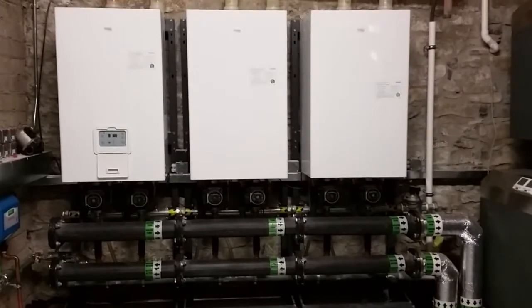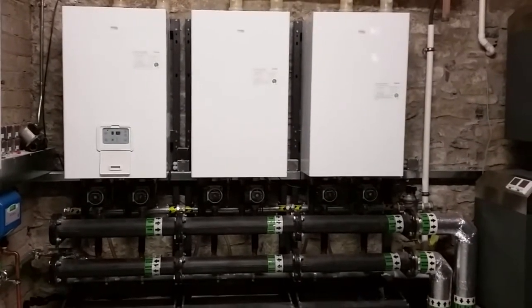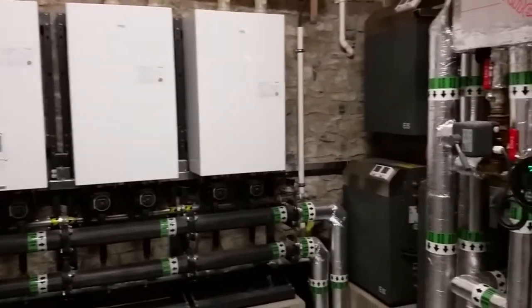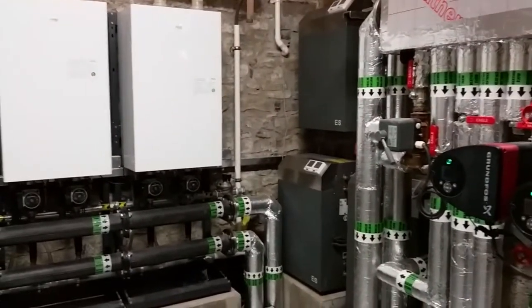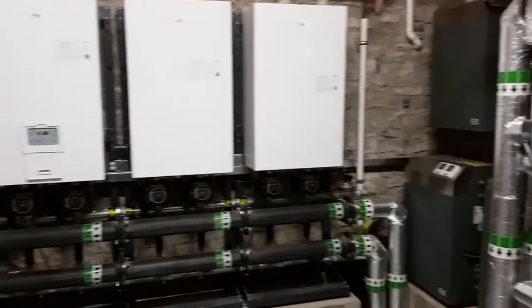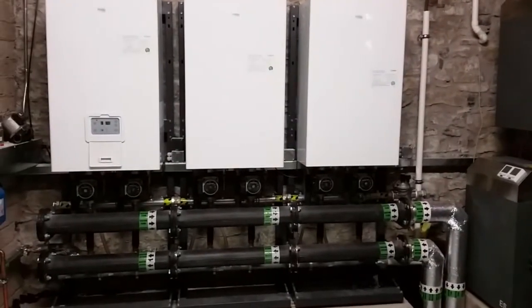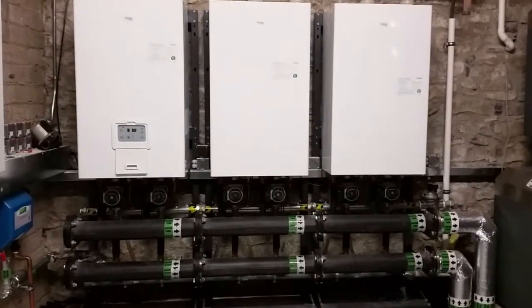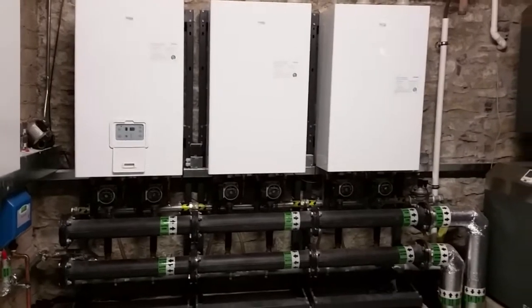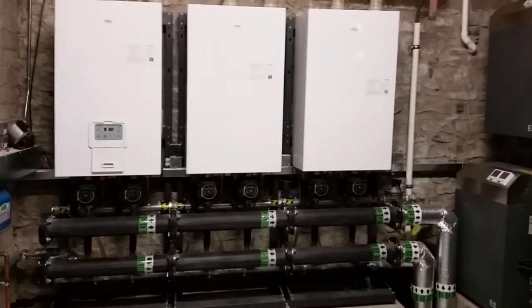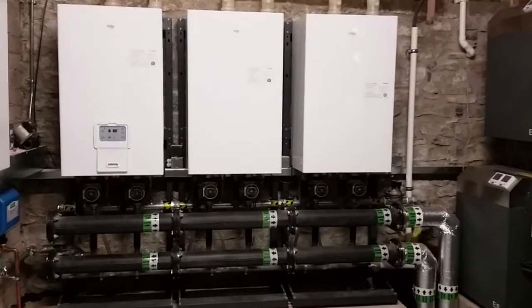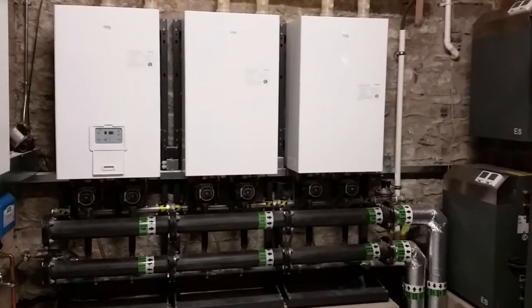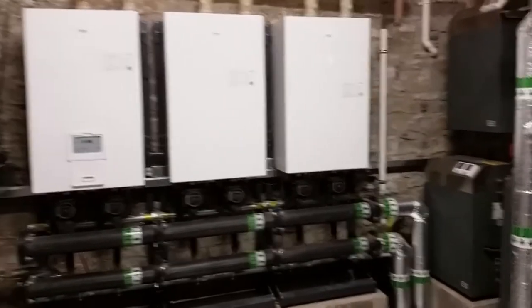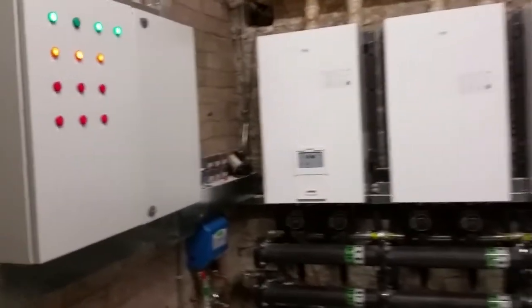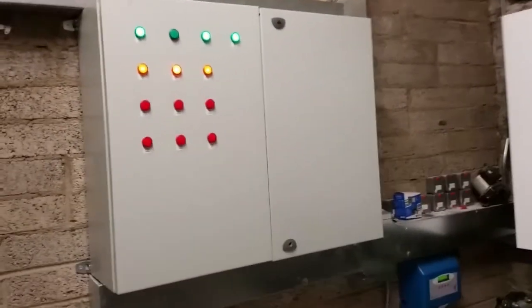When there's just a central heating call, the heat pumps are well able to handle the full load. But if colder weather kicks in, or a lot of the zones are calling, because there's 12 zones in the premises, if they're all calling, then the boilers will all kick in to work together to bring the building up to temperature. The whole system is controlled by an energy awareness building management system panel.